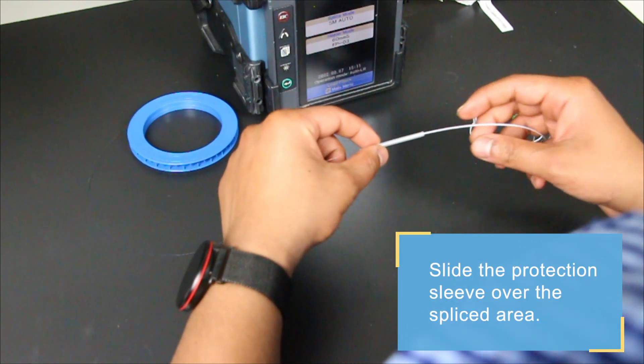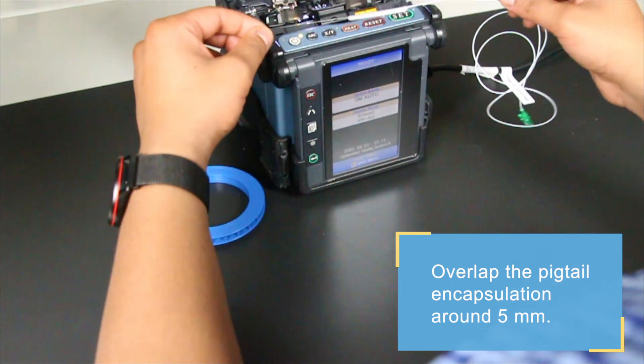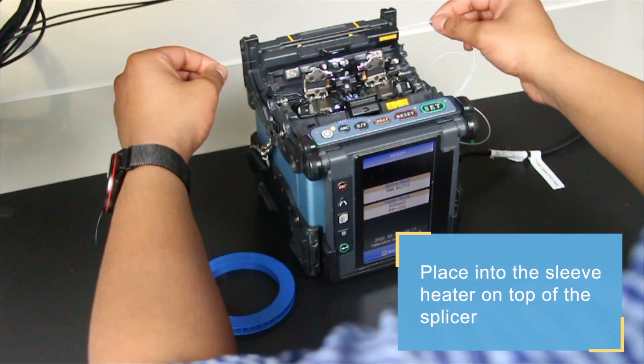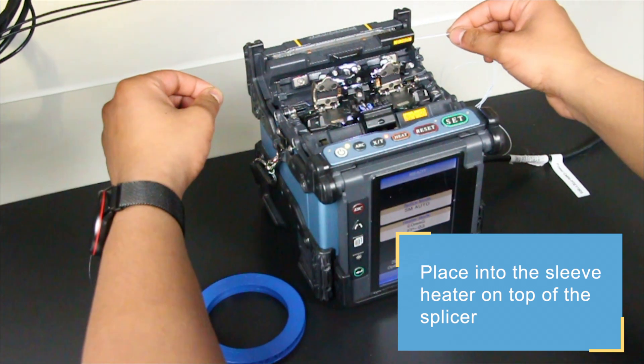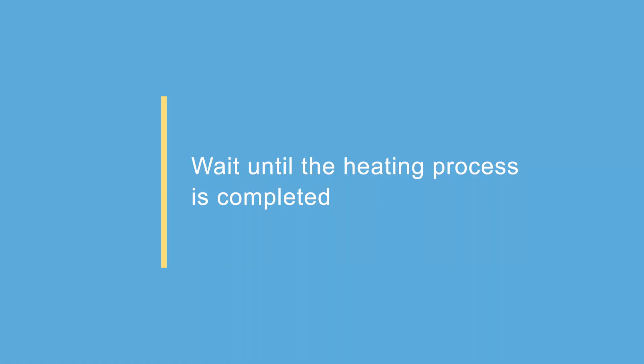Slide the splice protection sleeve over the spliced area. Seal the splice protection sleeve by heating it up. To do so, place the splice-protected fiber in the sleeve heater located on top of the splicer. The heating will start automatically. Just wait until the process is finished.